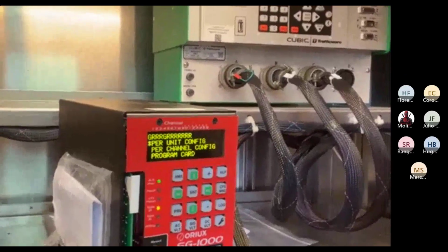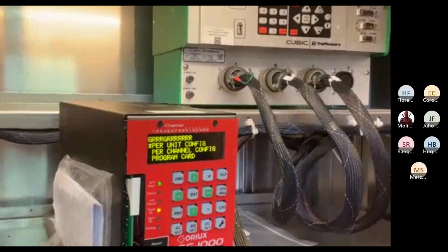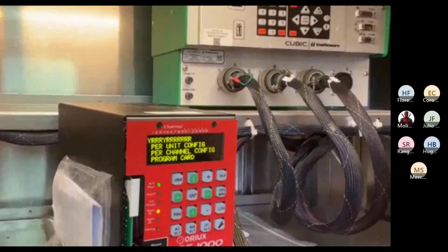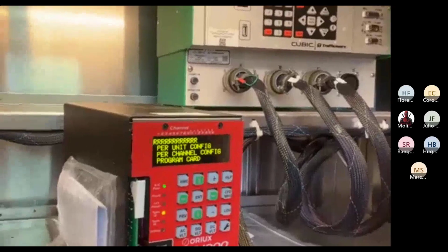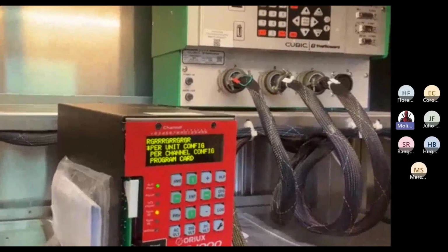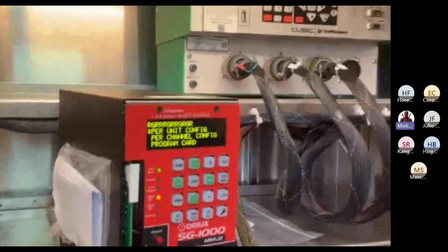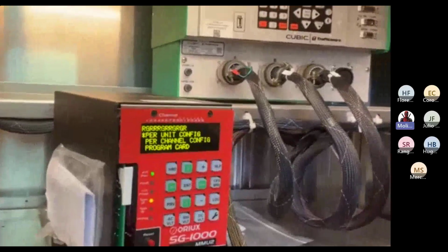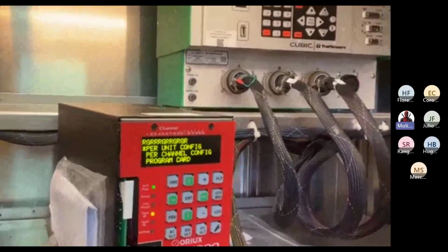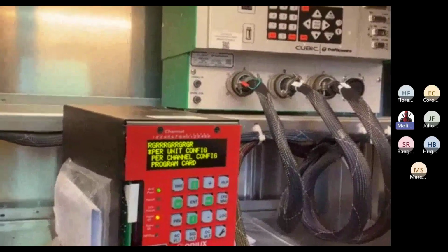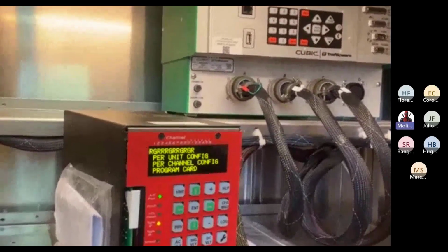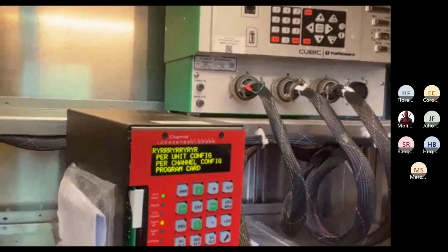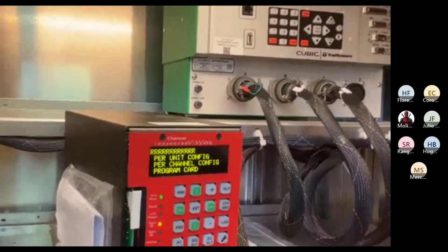You look at the fault because you want to note the fault down, and you want to note the status of any voltage that's not normal. Or just note everything down, just in case. That's a plus. Most units have it, but this one is a whole different level of what they're giving you. Some of them just give you the brownouts and a range of voltages when it's shut down.